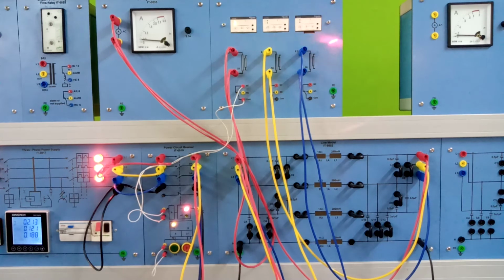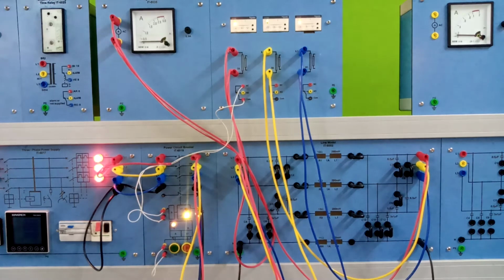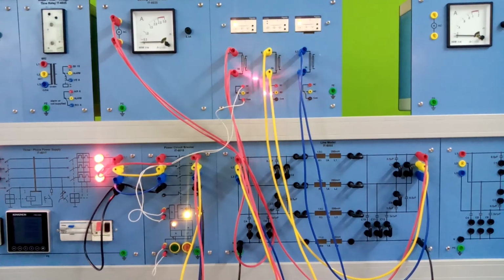Okay, so now all three relays are operating and initializing, and you can see this one is ready, this one is ready, this one is ready. So let's increase the load and simulate a three-phase short circuit. Okay, so again these two relays are showing trip, and this one has tripped but is not showing any value. So it's okay, the main focus is on the power circuit breaker, and you can see that it has tripped, so that's okay. So it was the short circuit among all three phases.